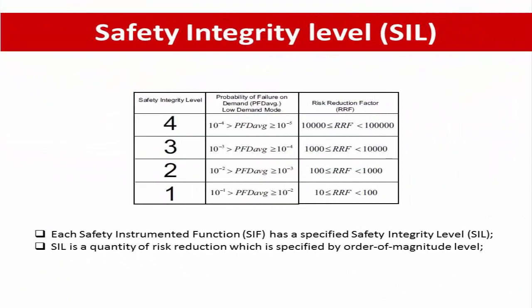What is the Safety Integrity Level, or SIL? Each safety instrumented function has a specific SIL which is necessary to achieve functional safety. The consequence severity and the likelihood or frequency of a hazard determine risk and the required risk reduction. In some cases the risk is within the tolerable level so no risk reduction is needed, but in other cases even considering existing outer safety protection layers, the risk is still at an intolerable level.